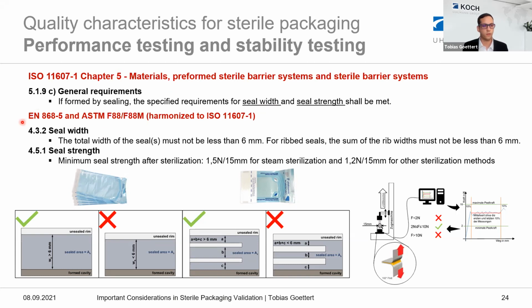And therefore we have a standard, it's called EN 868-5. And it says the total width of the seal must be at least 6 millimeters. So in our experience, our customers use mostly between 6 and 10 millimeters, and the most common was 8 millimeters. And sometimes there are also pouches or ribbed seals. It also says the sum of the ribs has to be 6 millimeters.